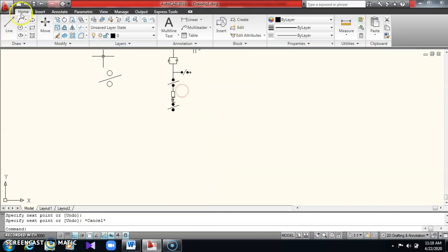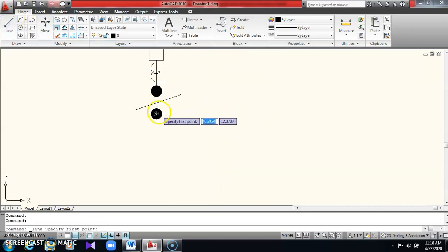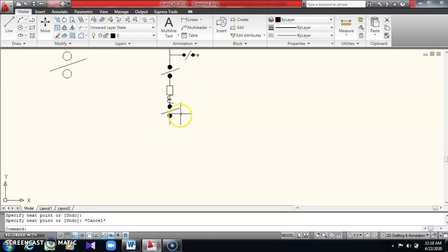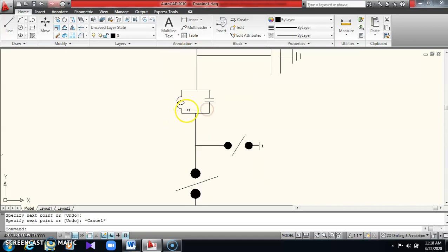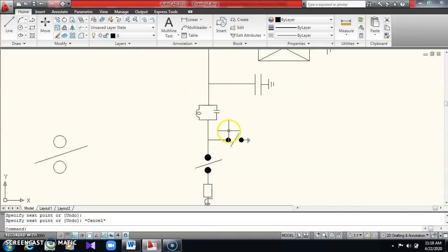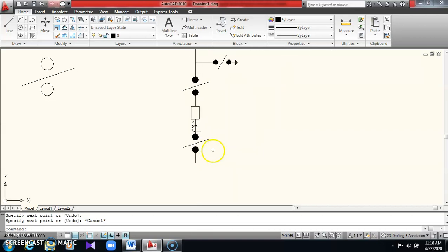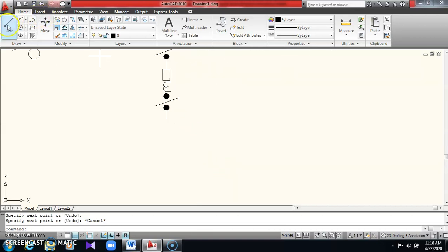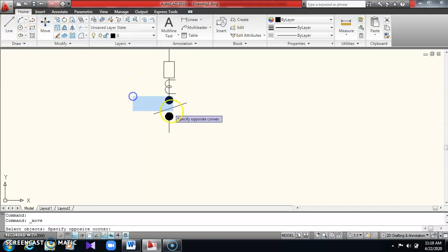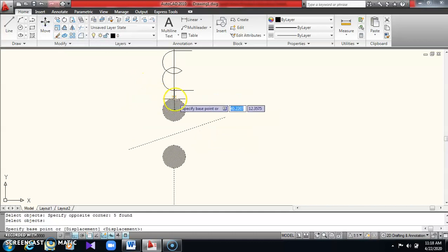Okay. So we have provided all those, right. So these are all the incoming line. This is called wave trap, coupling condenser, earth switch, isolator, circuit breaker, isolator. Right. This is connected to double bus bar actually. So now if it is double bus bar, now isolator will split. So better I'll draw two isolators, it will split actually.